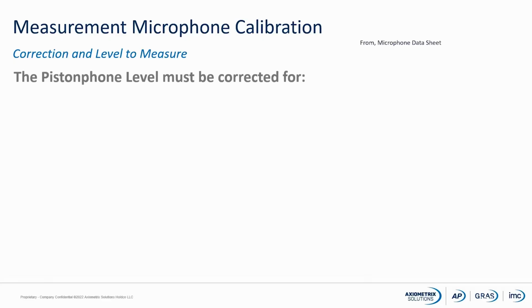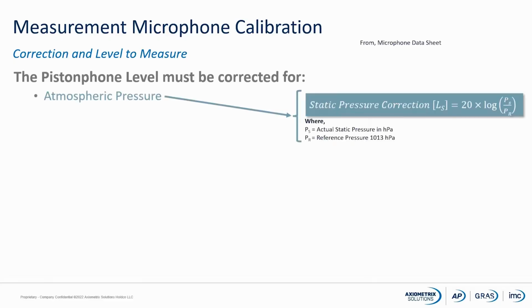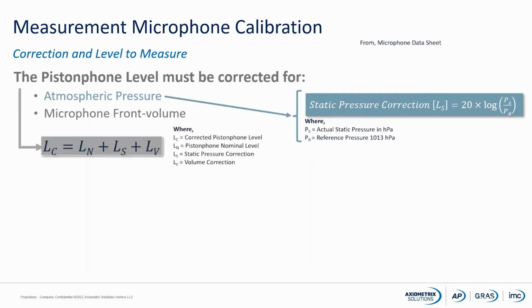When we are doing calibration, then we have to remember that our piston phone level must be corrected for, first of all, the static pressure. So we have to look at today's static pressure, and then do a correction for that. We also have to correct our piston phone for the front volume of the microphone. And in the end, we will end up with the piston phone level, or the level the piston phone is giving us, LC.